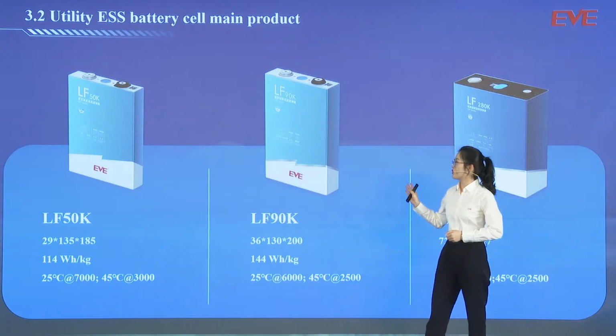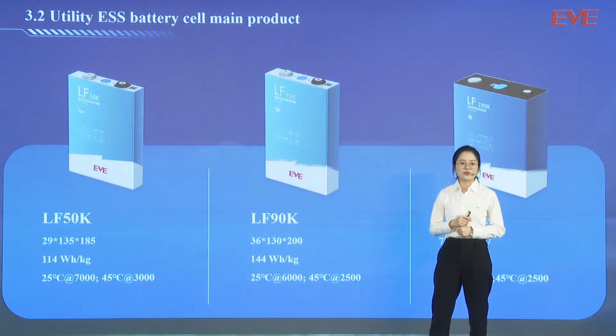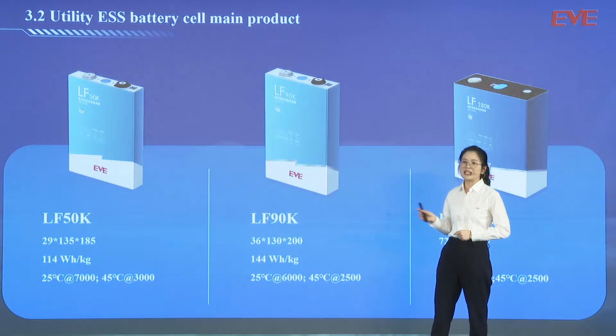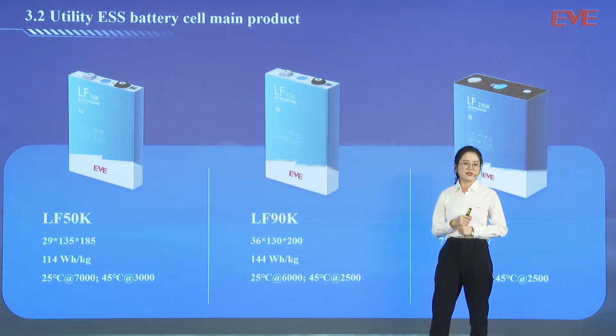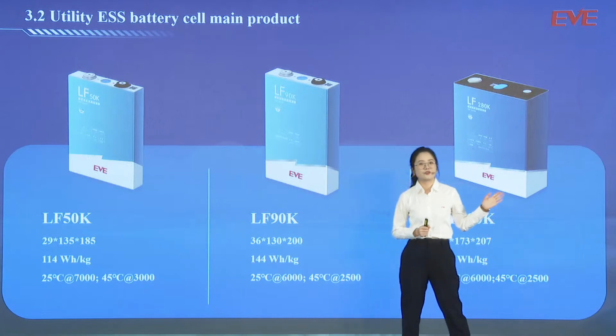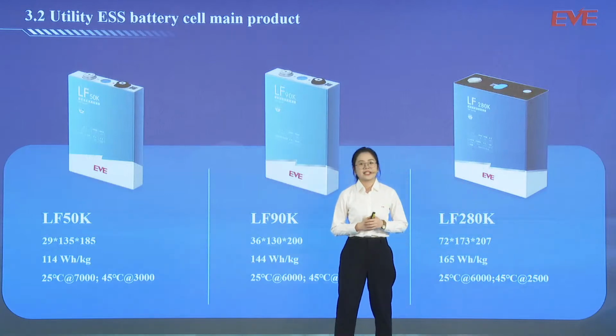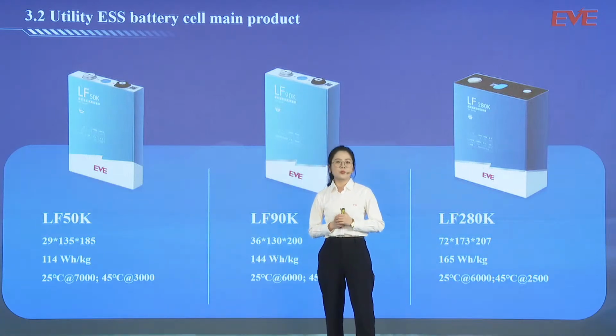For the LF50K, it's mainly used for peak load and frequency regulation applications with 2C charge and discharge. For the LF90K, it's mainly used for peak load and frequency regulation with 1C charge and discharge. For the LF280K, it is considered for 0.5C charge and discharge peak load shifting.